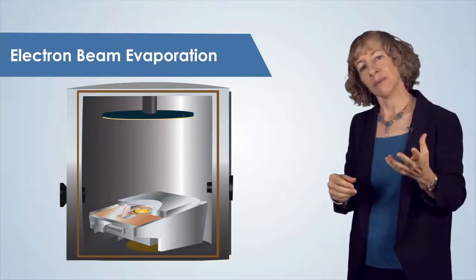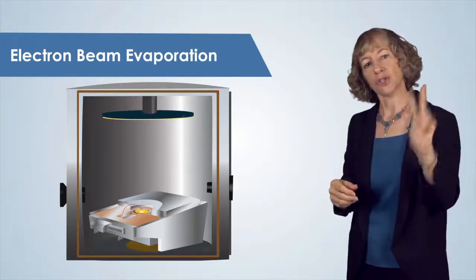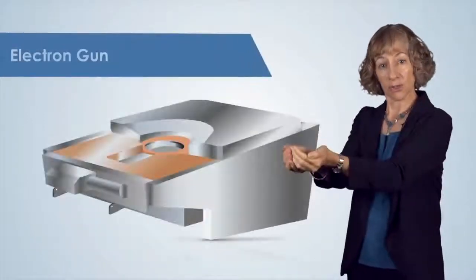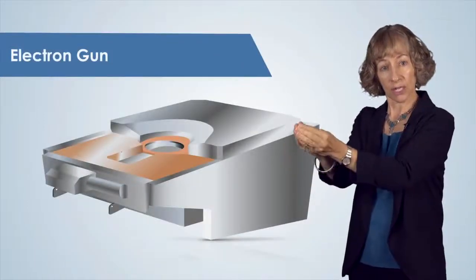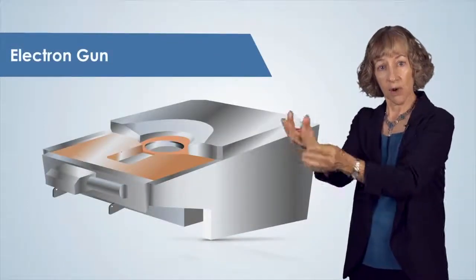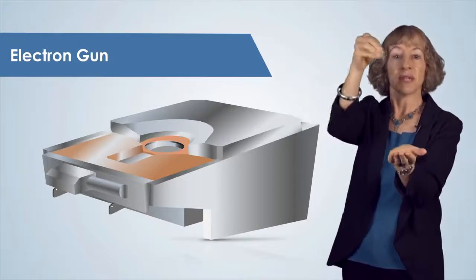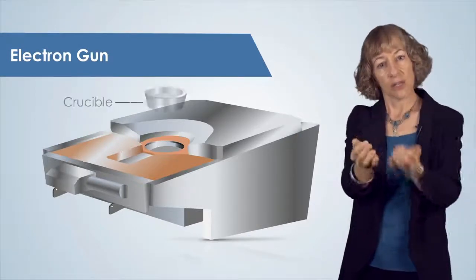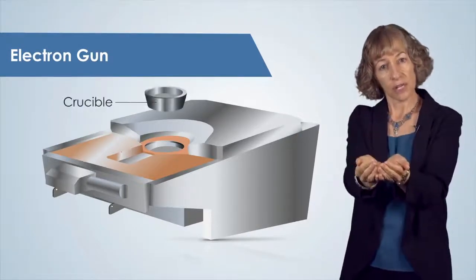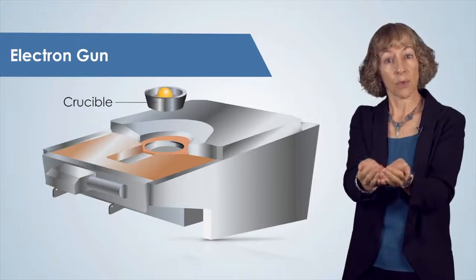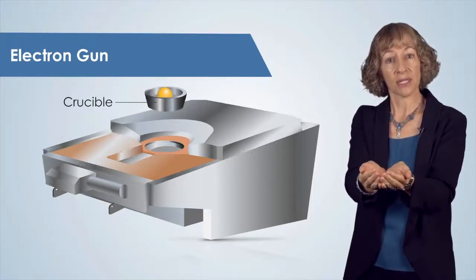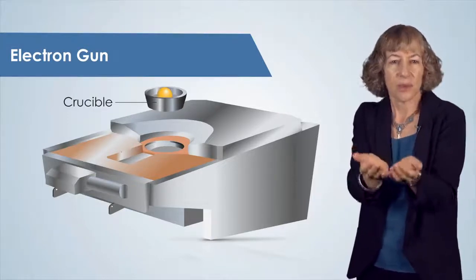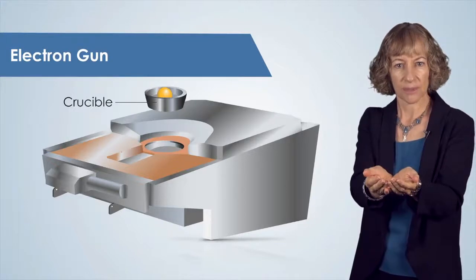An e-beam evaporator has two main components. First is the electron source or electron gun, which produces the beam of electrons. Second, the crucible is where the source material that we want to evaporate is contained. This is like the boat for thermal evaporation.